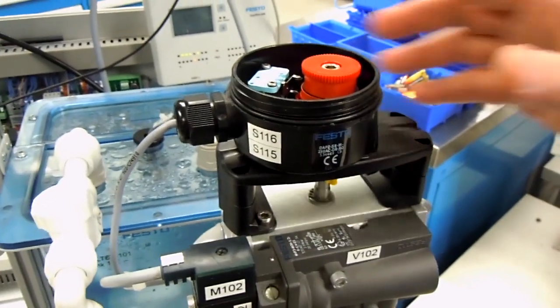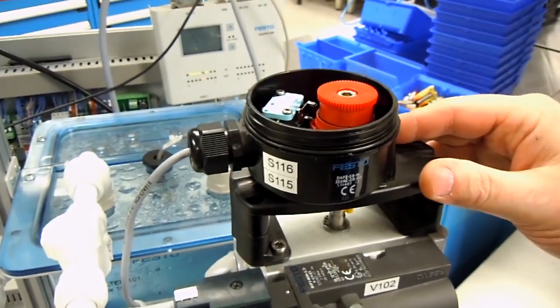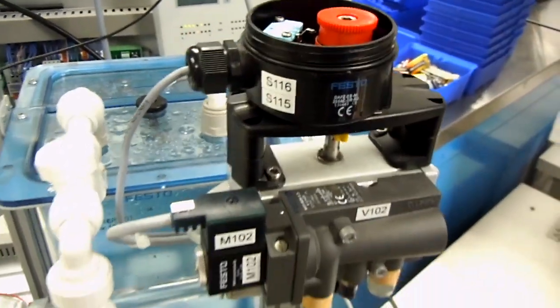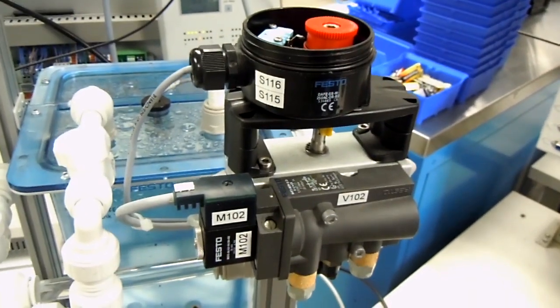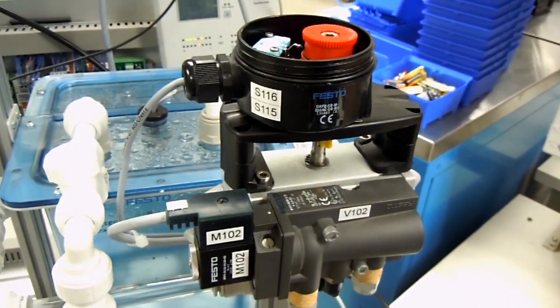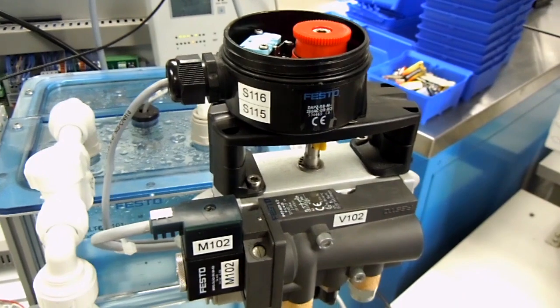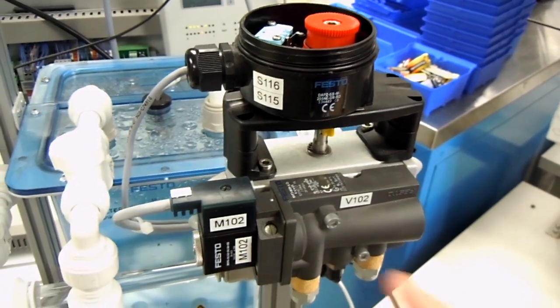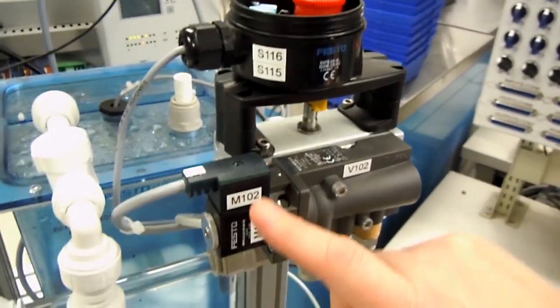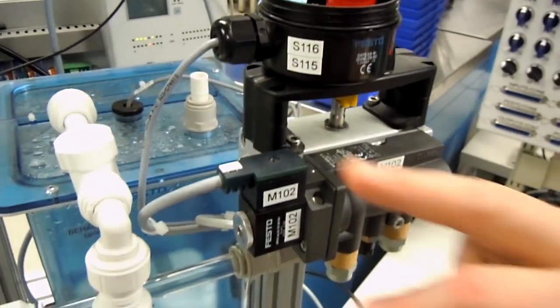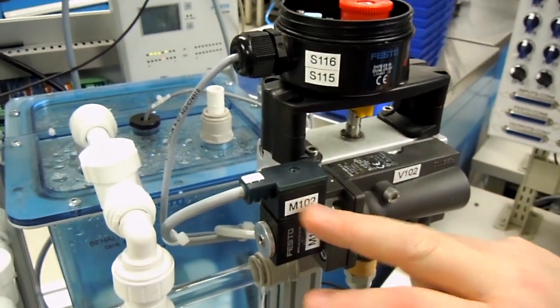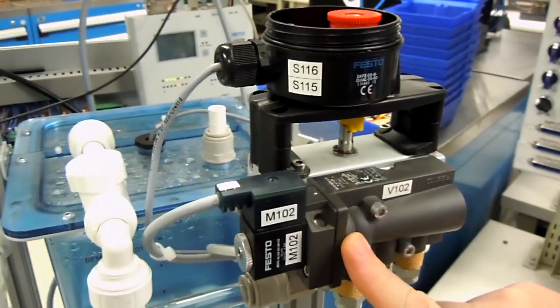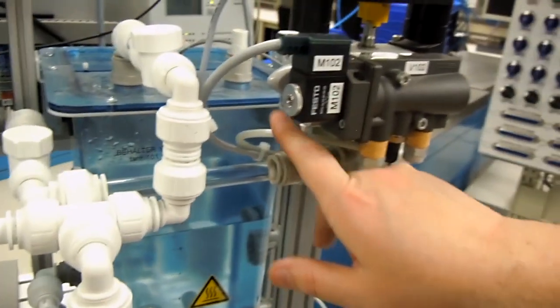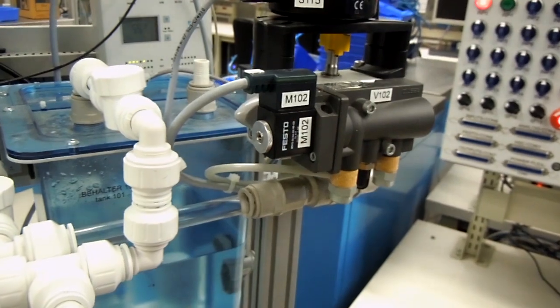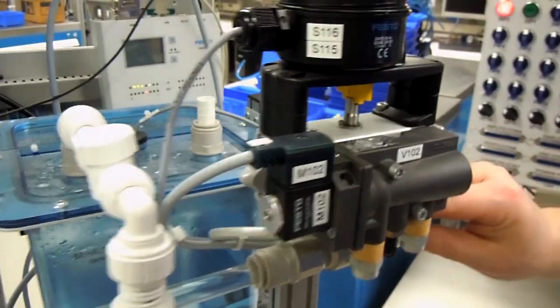Alright, the next thing I'm going to talk about is the process ball valve, which is this whole unit here. It's an electro-pneumatic device, which means it's controlled with an electrical signal and a pneumatic air supply. The electric signal is to this solenoid valve, and there's a 24 volt signal. When I energize it, it turns on this valve, allows air to flow into here, and the air is coming from tubing down to here. That's why you have to have an air supply.